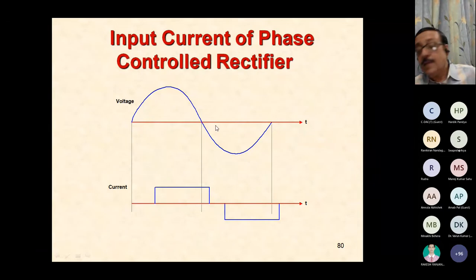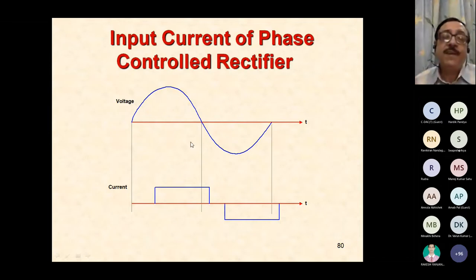This is an example of a worst condition, where this is a phase control rectifier input current. It's a flat topped current which gets shifted on the right hand side away from the zero crossing of the voltage depending on the firing angle of the converter. So in this case, as I change or increase the firing angle, power factor is degraded because of the displacement of the fundamental current. That is number one. Number two is because there is already a lot of harmonics in this, typically 33% harmonic. That is the second cause of degradation of power factor.